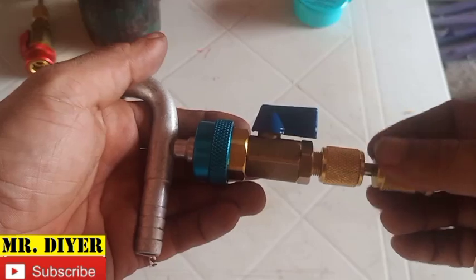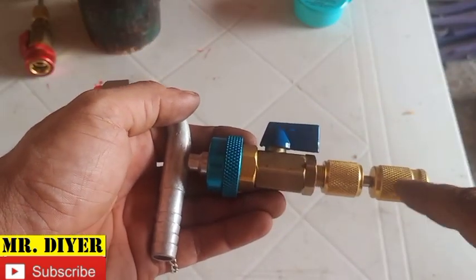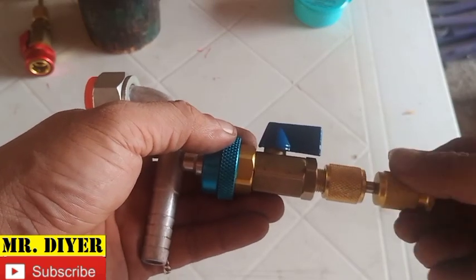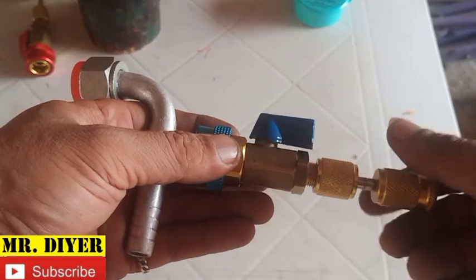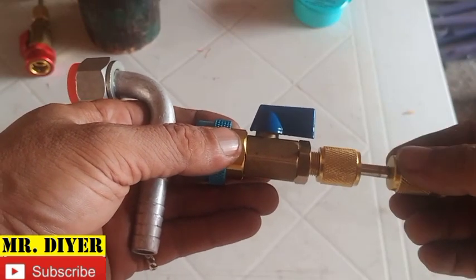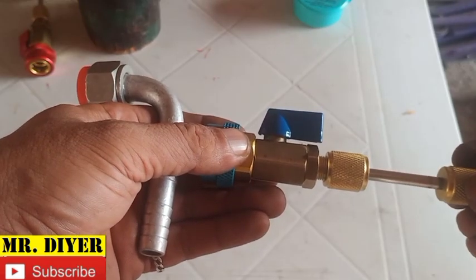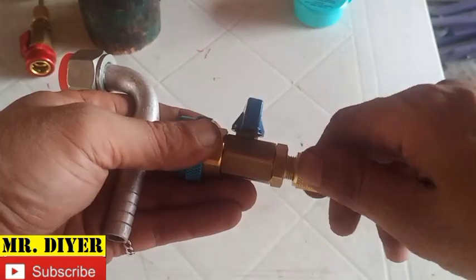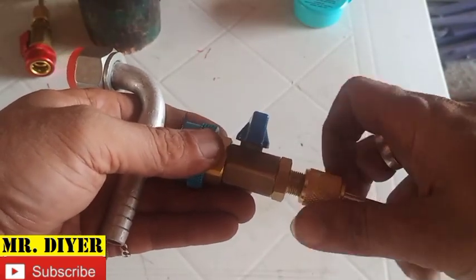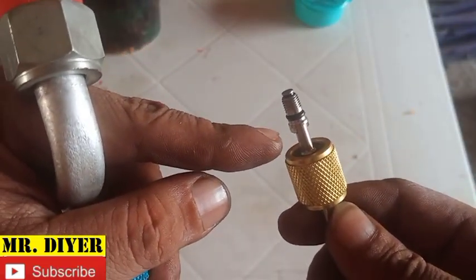More often than not, the refrigerant inside is going to push the Schrader valve as well as this tool outwards. In this case this is just for illustration purposes so there's no refrigerant inside. We'll try to pull that slowly all the way out, close this valve, undo this cap, and as you can see the Schrader valve is there.